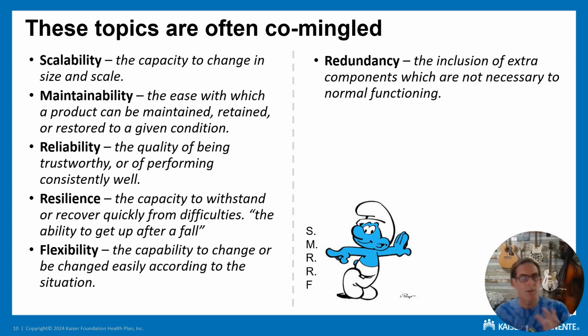So to wrap up the section on the Smurfs, let's remember that redundancy itself is a bad word. If we're adding something that's redundant, that means we're placing extra unnecessary components into our design. Anytime we do that, we should be serving one of these larger purposes: scalability, maintainability, reliability, resilience, or flexibility. And that purpose should always be very clearly articulated within the project requirements. Because redundancy costs, and it's not just capital costs, there is an operating cost.